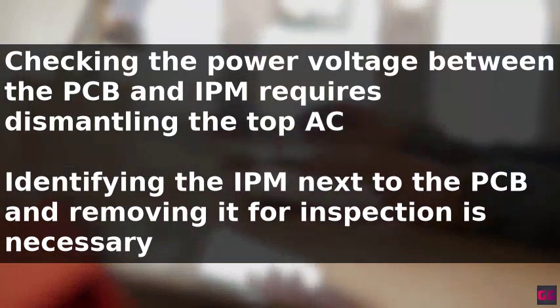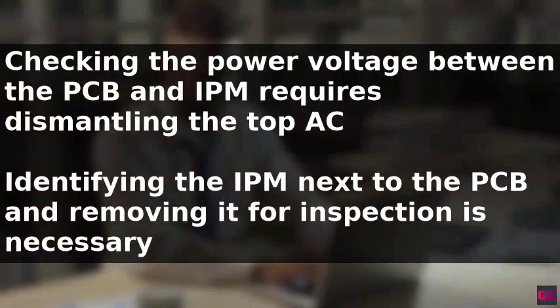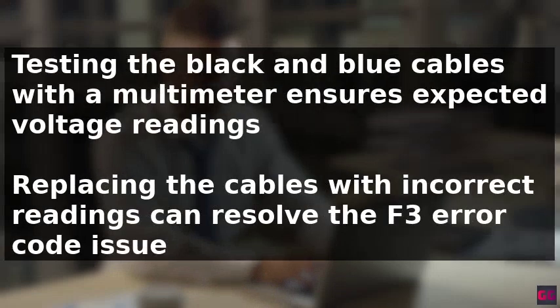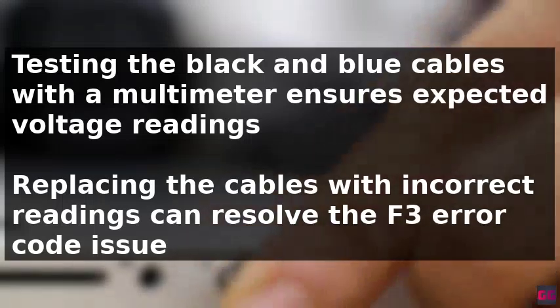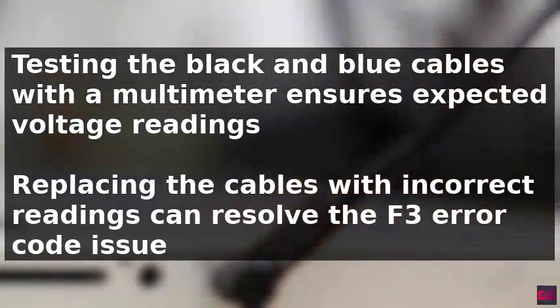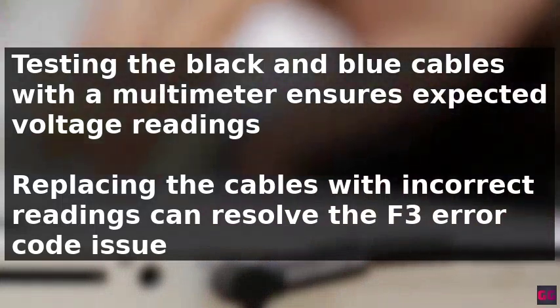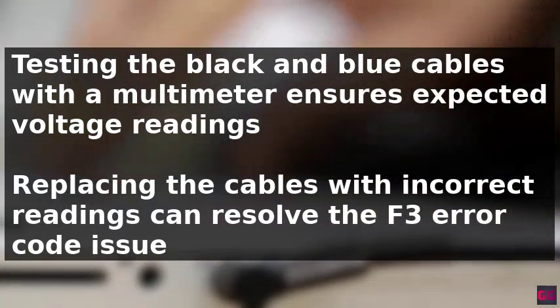Additionally, checking the power voltage between the PCB and IPM is necessary. This requires dismantling the top of the AC, identifying the IPM next to the PCB, removing the PCB from the unit, and inspecting the blue and black connectors for damage. The black and blue cables between the PCB and IPM should be tested with a multimeter to ensure they register the expected voltage readings of 5 volts and 15 volts. If the readings are incorrect, replacing the cables can resolve the issue.